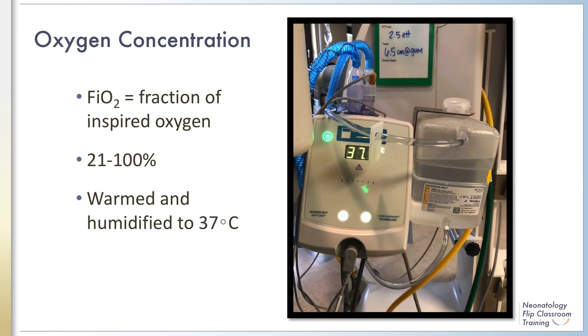Inspired gas is first warmed and humidified using an external device before being delivered to the patient. Humidity is important for maintaining mucociliary clearance, which is compromised by the endotracheal tube, preventing airway drying, and aiding thermal regulation, especially for smaller infants. Higher gas temperatures increase water vapor capacity, which can lead to condensation in the circuit or endotracheal tube, causing the patient to gag and leading to auto-cycling. Therefore, the temperature and humidity of inspired gas must be carefully regulated.